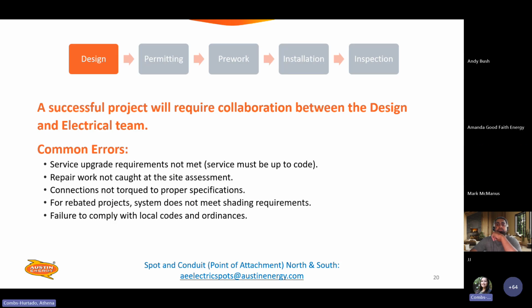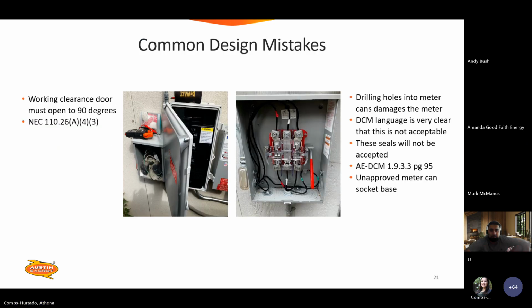All right, so a successful project will require collaboration between the design and the electrical team. Some of the common errors are service upgrade requirements not being met, repair work not caught at the initial site assessment, connectors not torqued to the proper specifications, and, for the rebated programs, the shade requirements not being met. Failure to comply with local codes and ordinances is also a common area. So please make sure that you're looking at our references to avoid these.